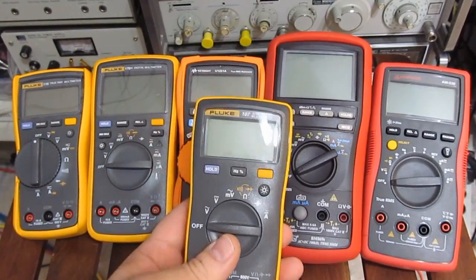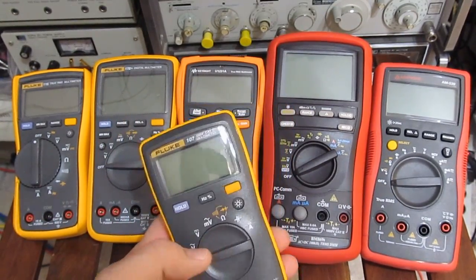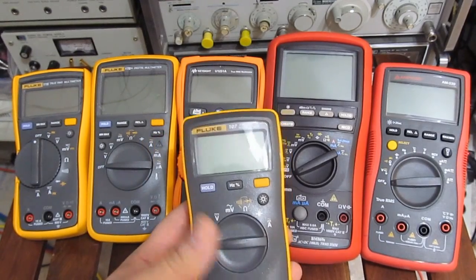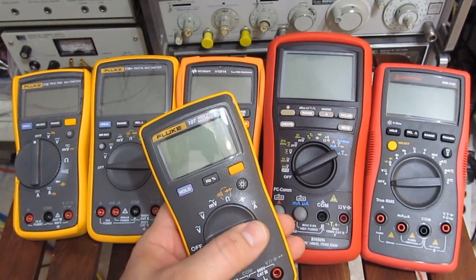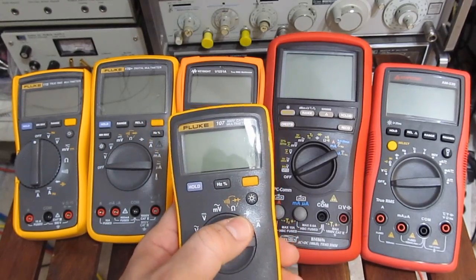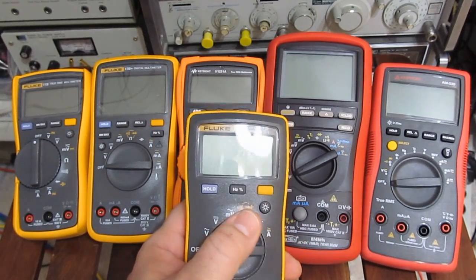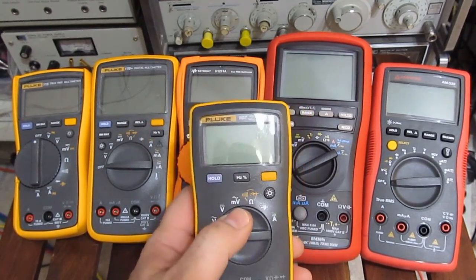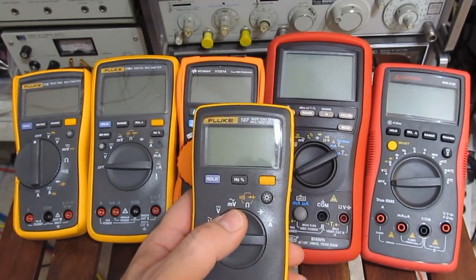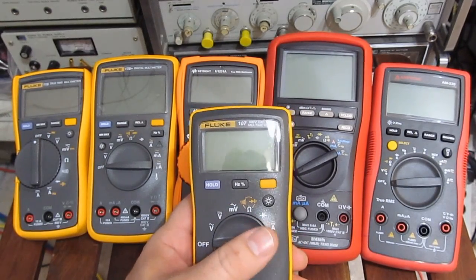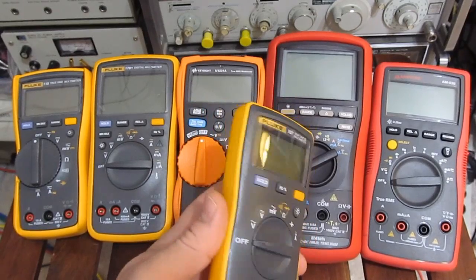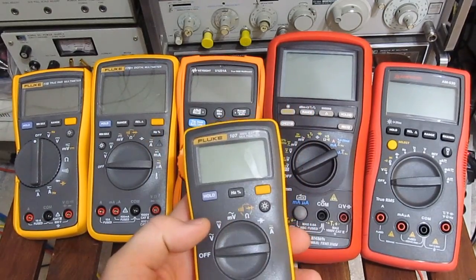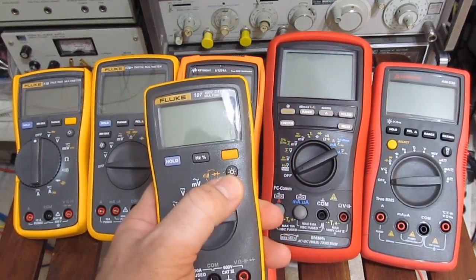If you're looking for something smaller, you have the Fluke 107. Again, fairly inexpensive meter. It's capable of measuring current. Also has capacitance, resistance, diode check. Can measure AC millivolts but not DC. Again, a no frills meter but very robust. I would choose this over the Fluke 101 only in that it has the backlight and the current input.